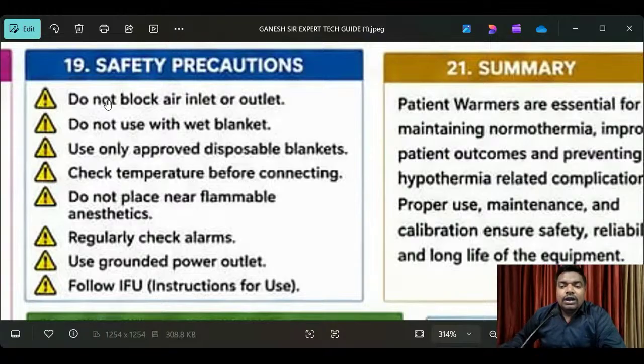See, do not block the air inlet or outlet. First point. And do not use with a wet blanket, and use only approved disposable blankets. Check the temperature before connecting, do not place near flammable anesthetics, regularly check alarms, use a grounded power outlet, and follow the IFU, the instructions for use. Very, very important. These safety precautions protect the patient and the equipment, and we should protect ourselves also. I hope you are getting it.